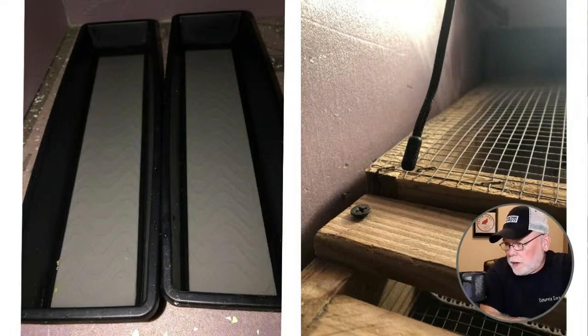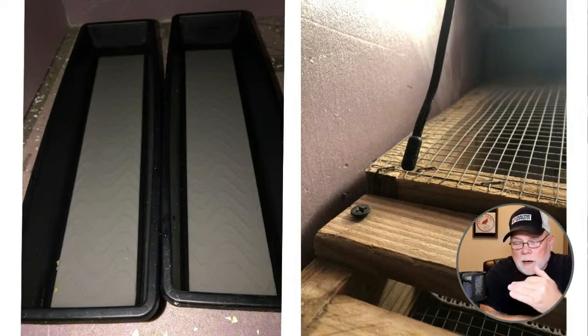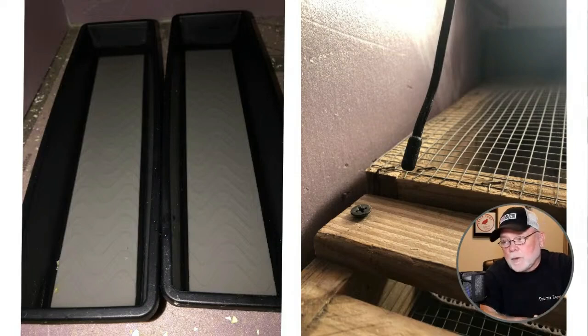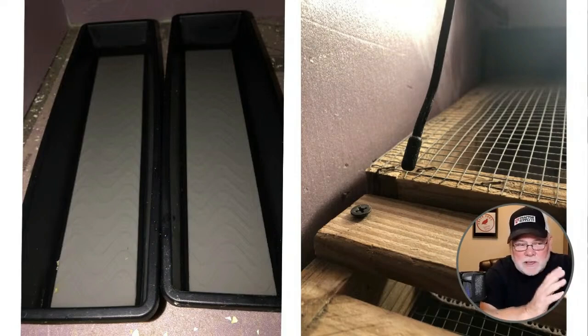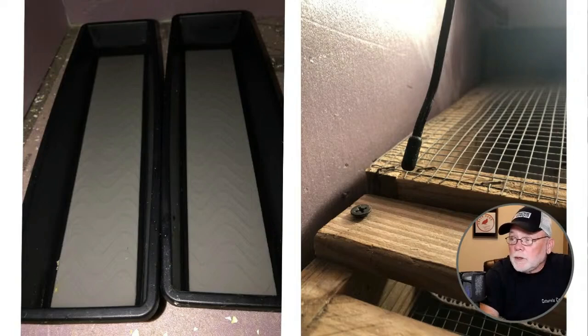And the other shot on the right is just showing the temperature sensor probe. I always keep that even with the top of the top hatching tray or the top turner if you're going to use it as an incubator also. And the reason for that is obviously heat rises. So you want that sensor probe to be in an area where, if you had it lower than this top shelf, it might get too hot.